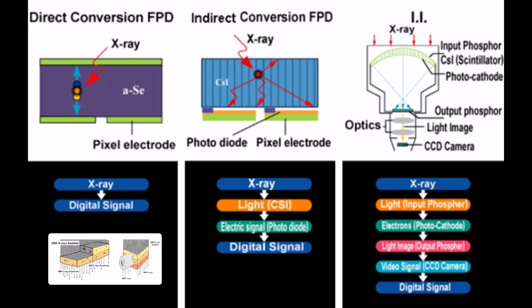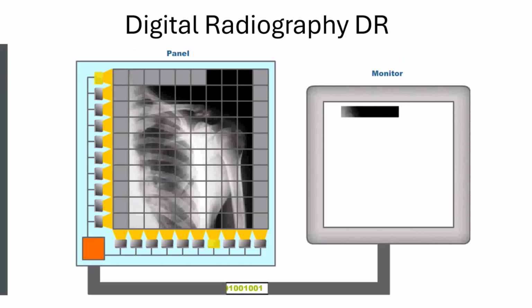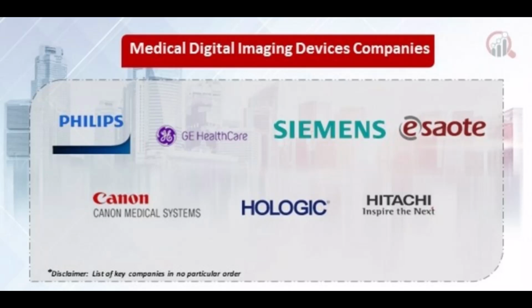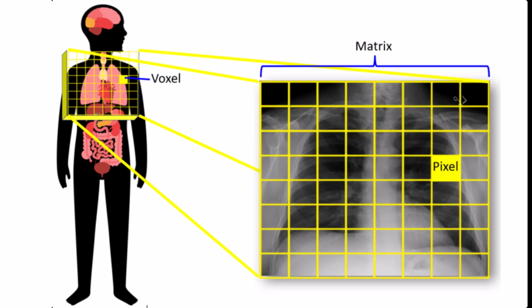Once an image exposure is captured in direct digital radiography, the imaging processing is basically the same whether the capture was direct or indirect, except for variances in processing that are dependent on the manufacturer's proprietary processing algorithms and technology. Each "pixel" in the receptor matrix has a fixed size and location. The energy from the exposure is captured at a specific pixel location on the image receptor matrix and creates data which can be mapped precisely to create digital images.